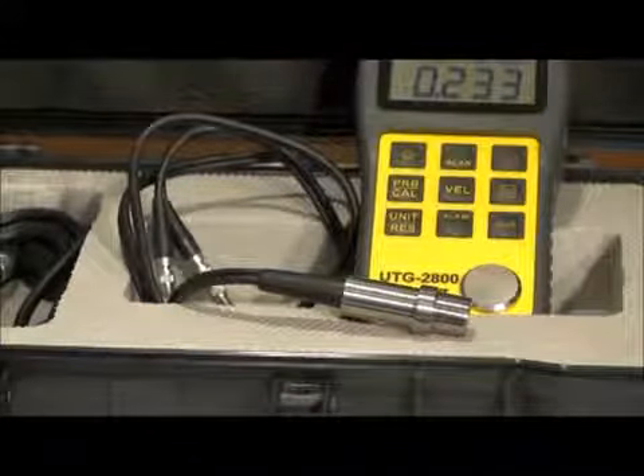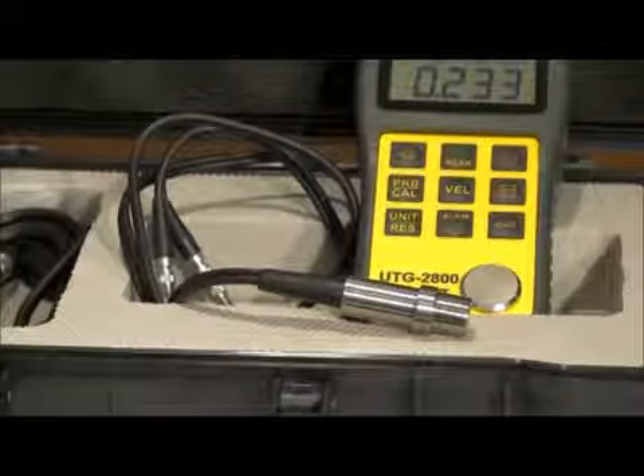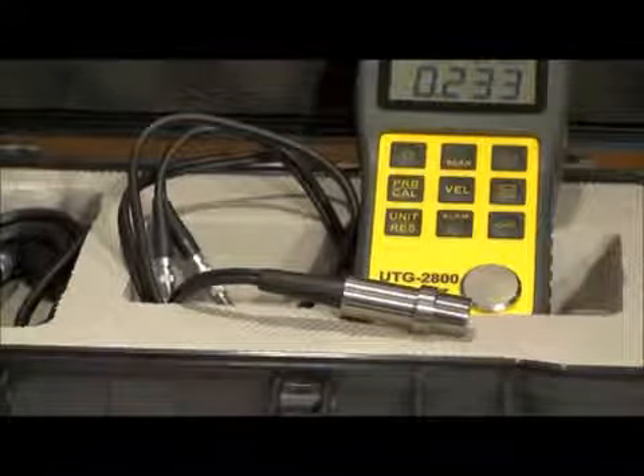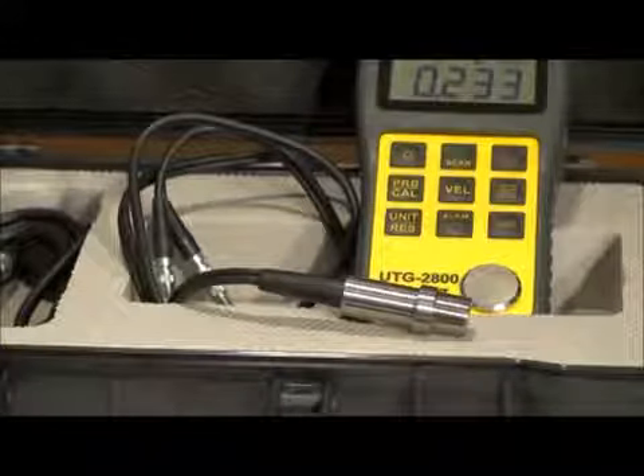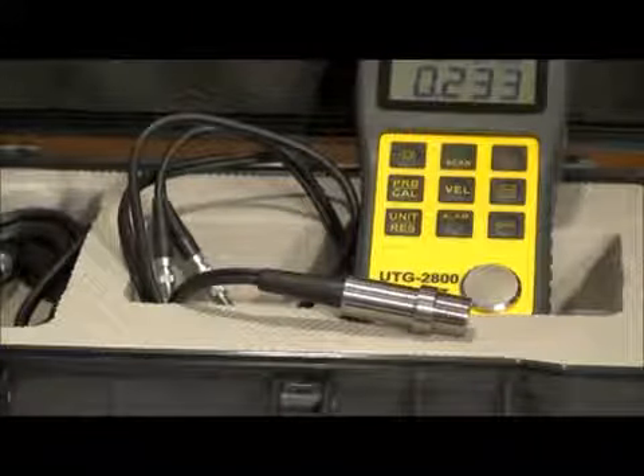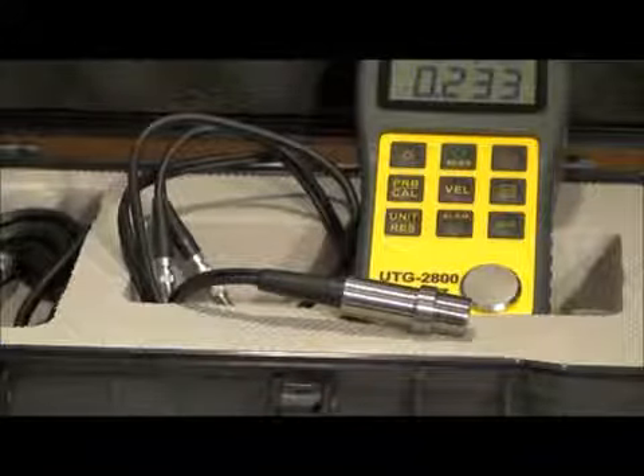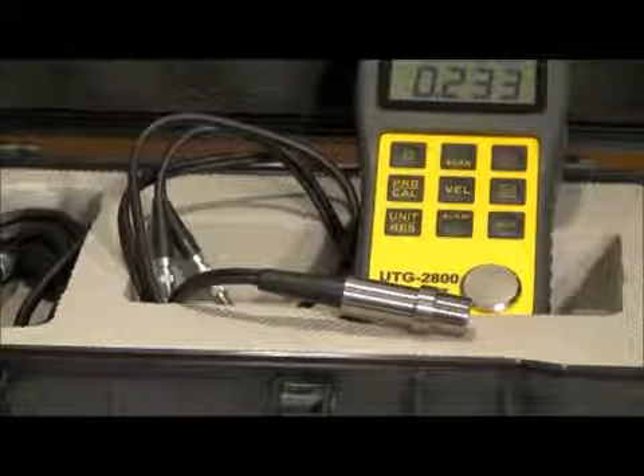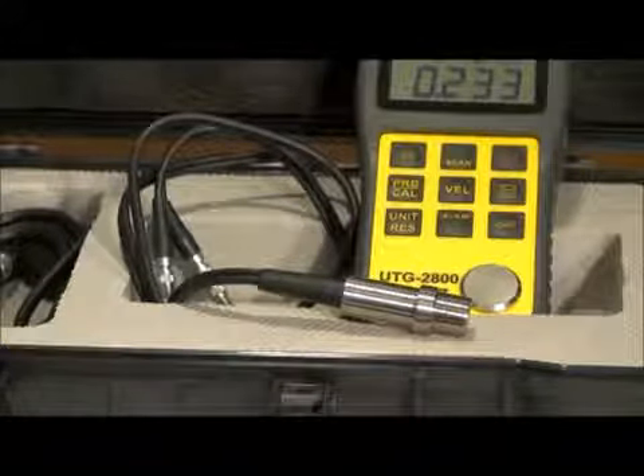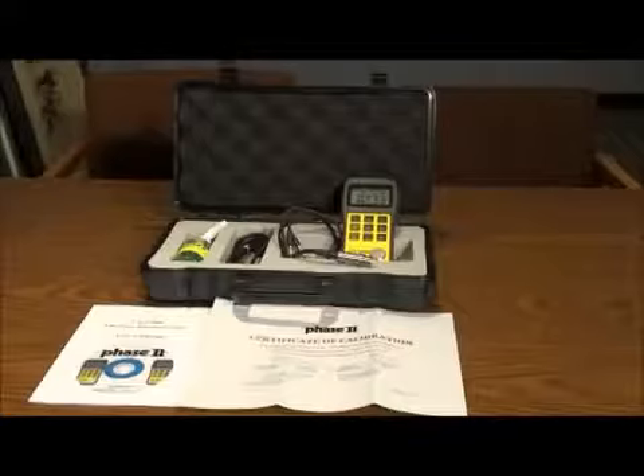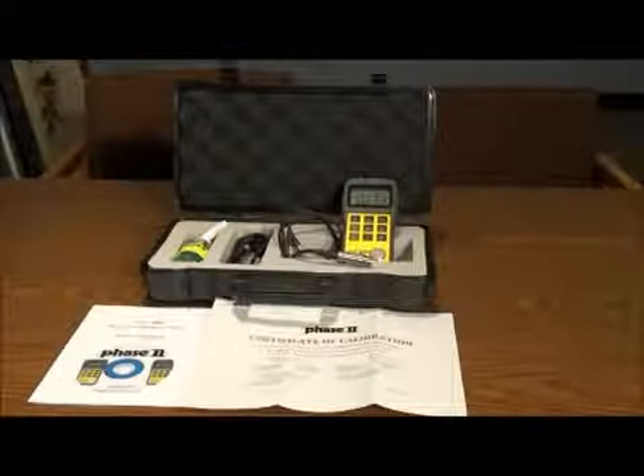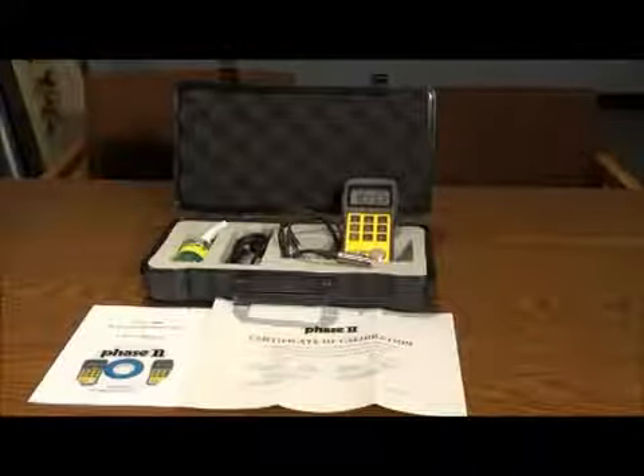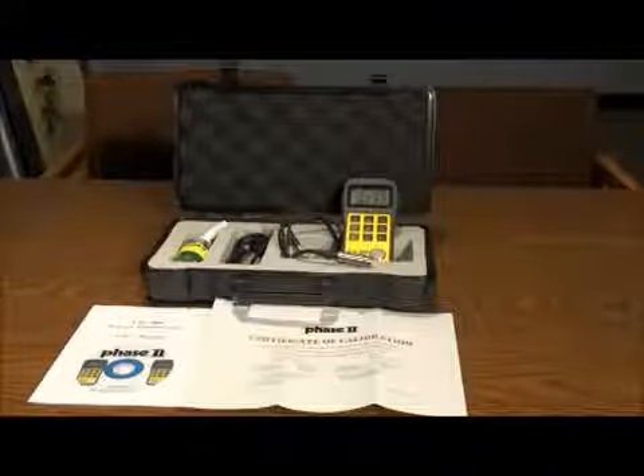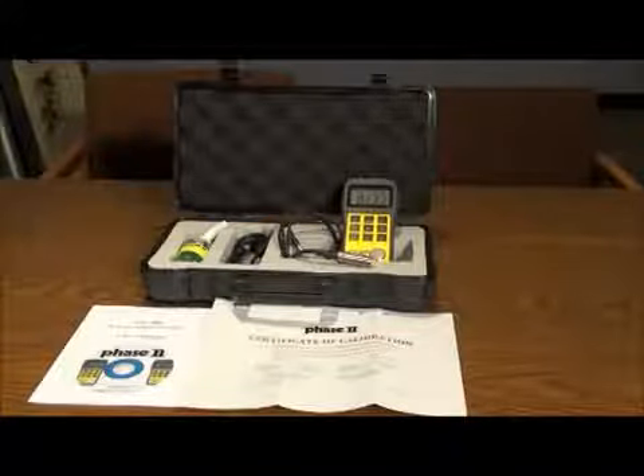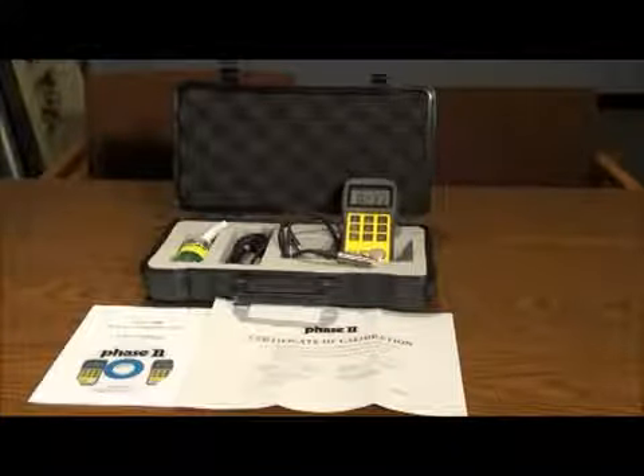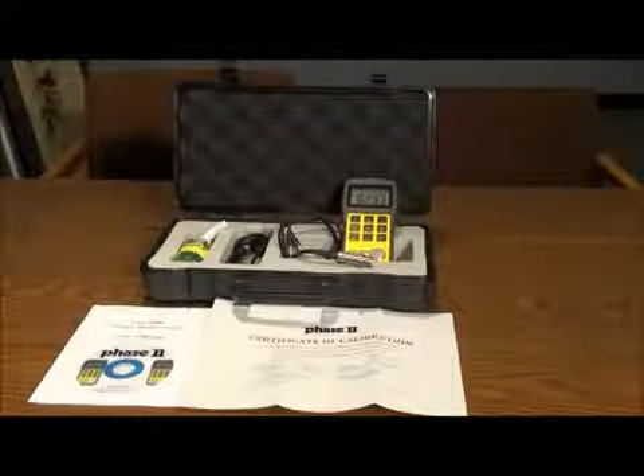Generally, the velocity of sound through the material to be tested is a known value and is supplied via chart in the manual. In the case of the UTG 2800, we have preset the unit velocity to read steel, which matches the material of the built-in test block. You always have the option to manually preset the velocity of any material. Each gauge is supplied with a 5 MHz dual sensor probe, bottle of couplant gel, 2 AA batteries, carry case, certificate of calibration, software, and operation manual.